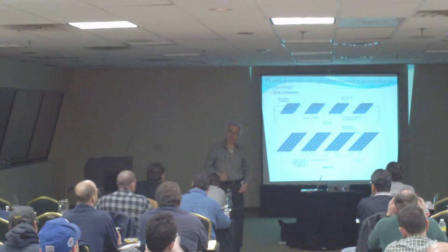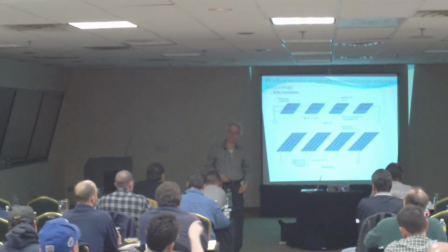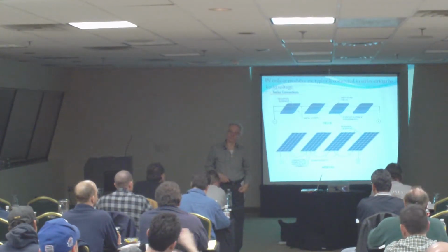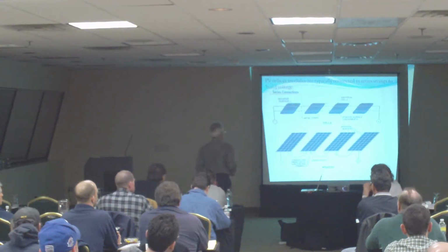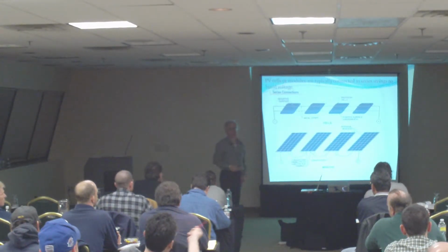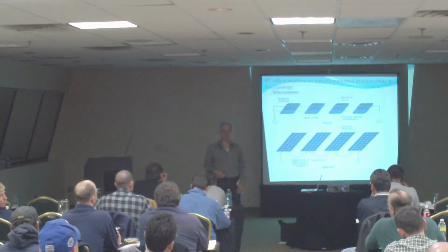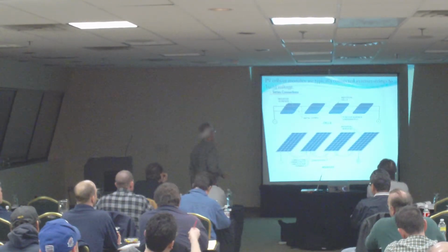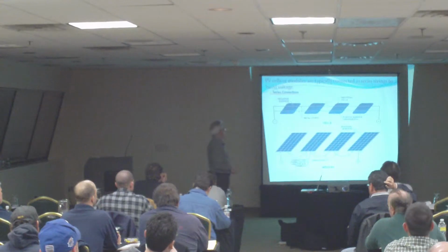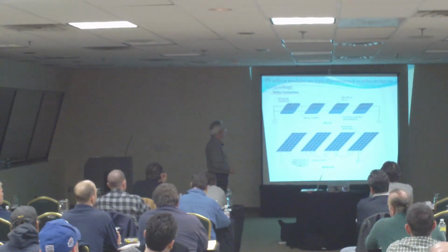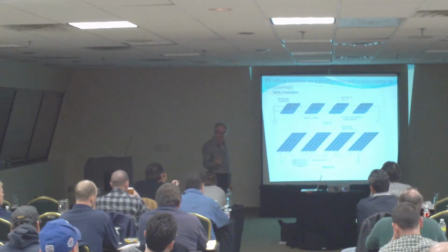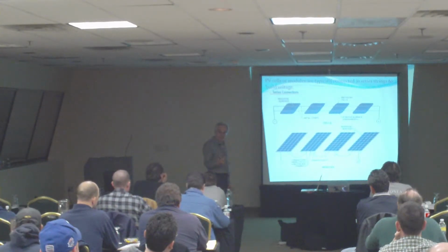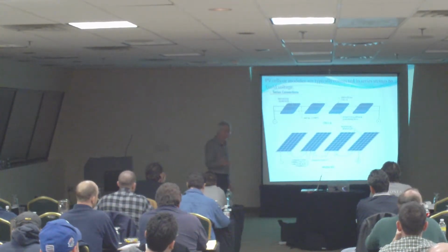Excuse me? You're not going to have 8.3 amps. When you connect those two leads to the inverter, that's when we're going to see the current, and from the illumination as well. You're not going to have 8.3 because that is the short circuit current. You just add the voltages here in series and have the voltages brought to the inverter. The voltage in here would be the measured voltage of the open circuit condition.